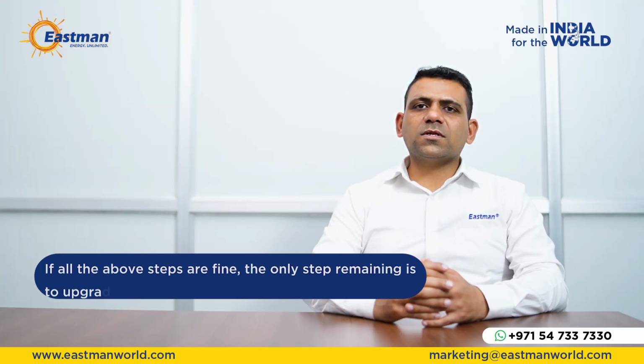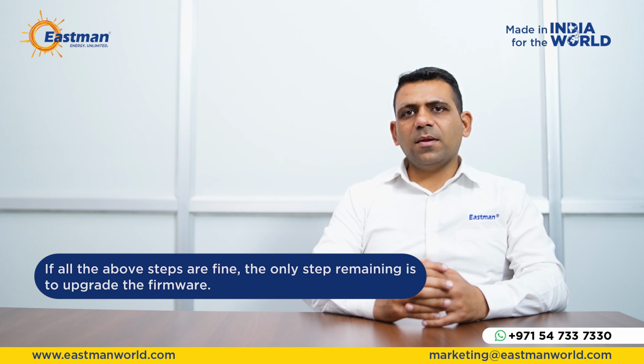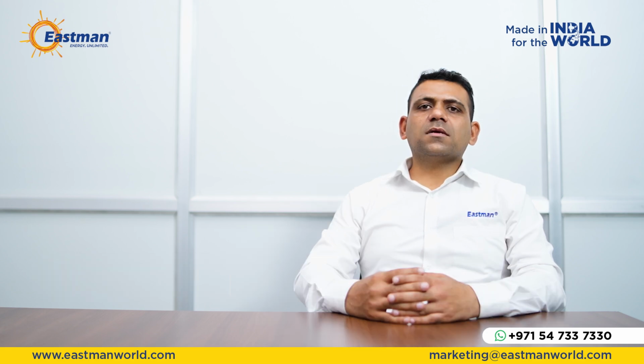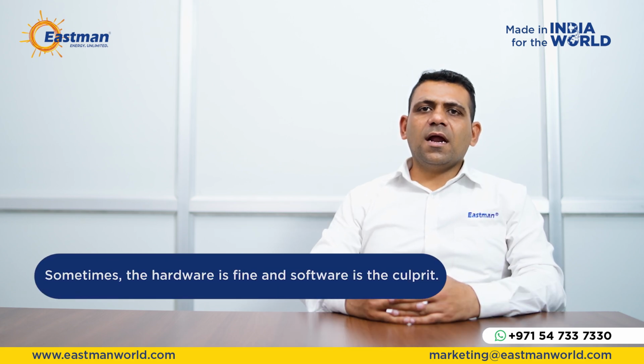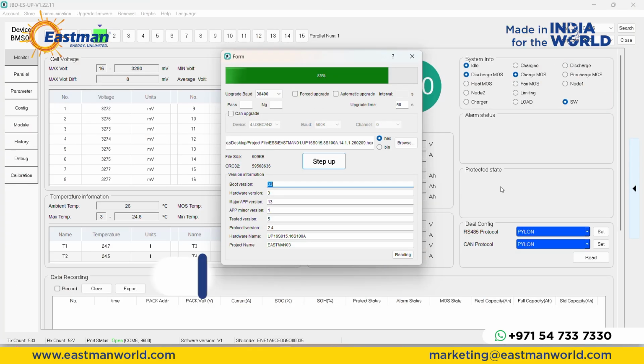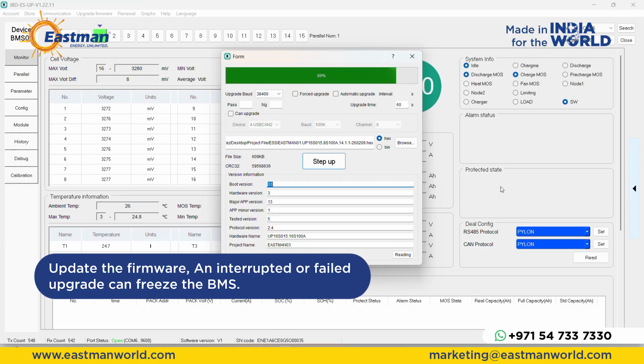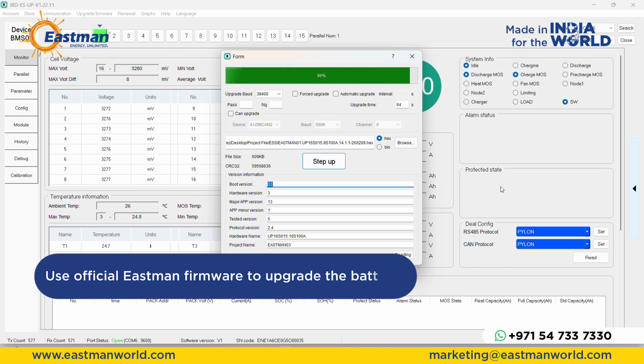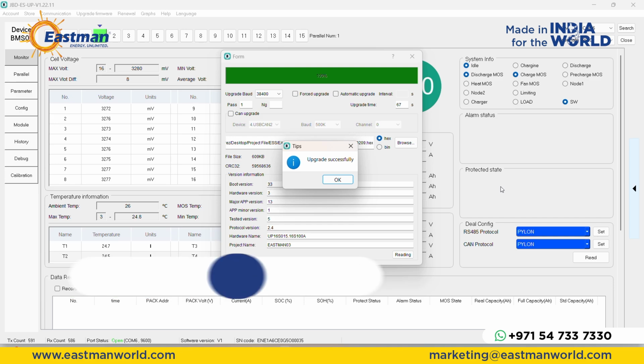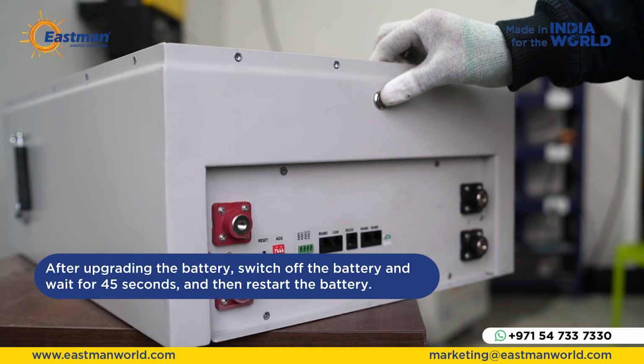If all the above steps are fine, the only step remaining is to upgrade the firmware. Sometimes the hardware is fine and software is the culprit. Update the firmware. An interrupted or failed upgrade can freeze the BMS. Use official Eastman firmware to upgrade the battery. Perform a hard reset. After upgrading the battery, switch off the battery, wait for 45 seconds and then restart the battery.